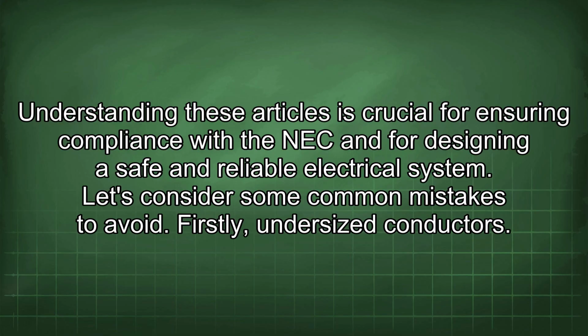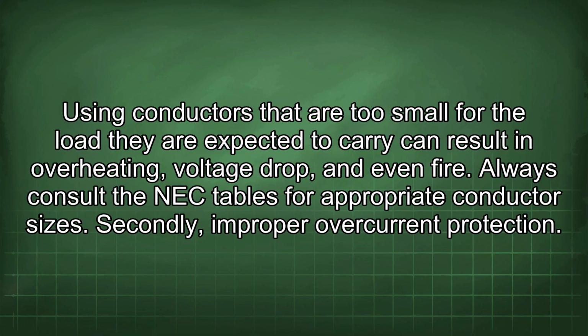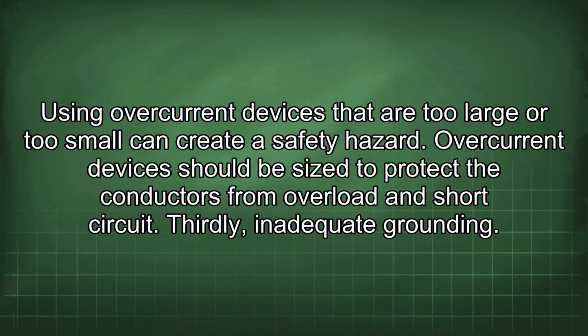Firstly, undersized conductors. Using conductors that are too small for the load they are expected to carry can result in overheating, voltage drop, and even fire. Always consult the NEC tables for appropriate conductor sizes. Secondly, improper overcurrent protection. Using overcurrent devices that are too large or too small can create a safety hazard. Overcurrent devices should be sized to protect the conductors from overload and short circuit.